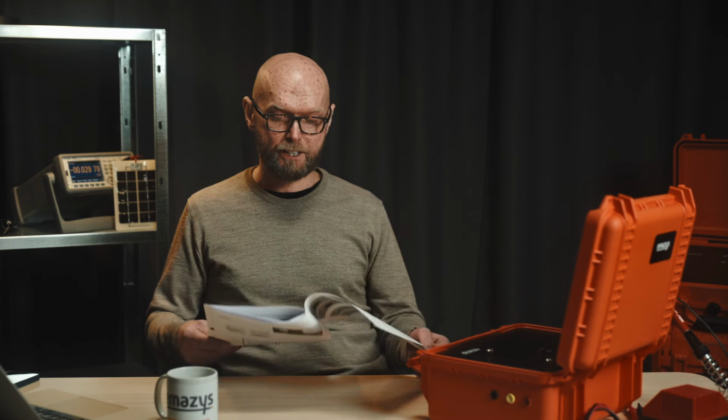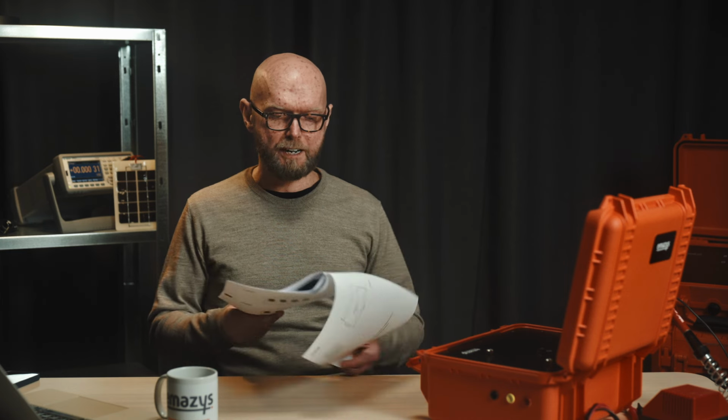Number 3, homogeneous long-term light absorber degradation. When it comes to actually discussing the solar cells themselves, we have something we refer to as potential induced degradation. That is probably the most well-known phenomenon of homogeneous power output degradation. It's something that happens over time as the potential of the solar panels is tearing down the low-quality solar cells.